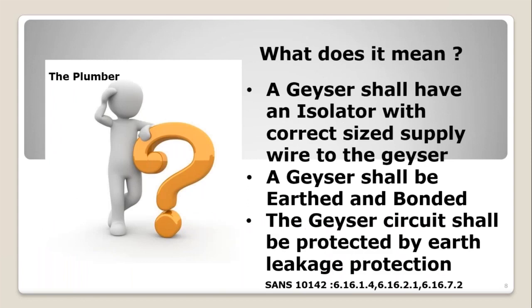The geyser shall have an isolator with a correct size supply wire to the geyser. That will be a requirement of a minimum of 2.5 square millimeters wire size. The geyser shall be earthed and bonded. The geyser circuit shall also be protected by earth leakage. There are references to those clauses. So guys, what does this now mean for the plumber himself? Next slide, Herman.